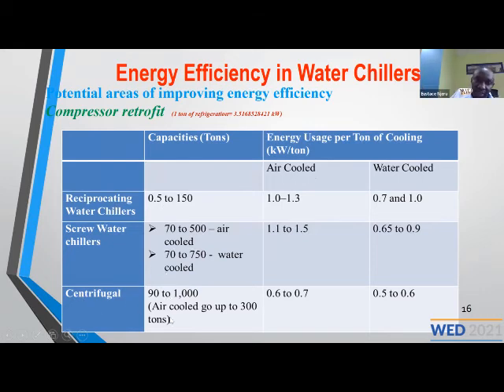For the centrifugal units, these are high volume and they are very efficient. They don't deliver a lot of pressure, and to deliver a lot of pressure, you need to use several of them. These are more like centrifugal fans, so you have to compress the refrigerant in series. But they are very efficient at very high loads, and they are easily controlled by VFDs.